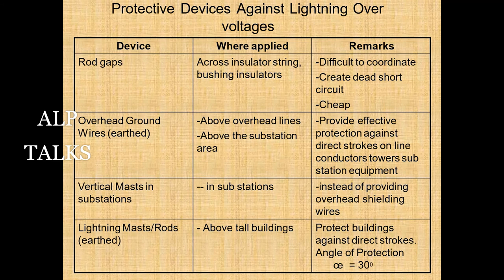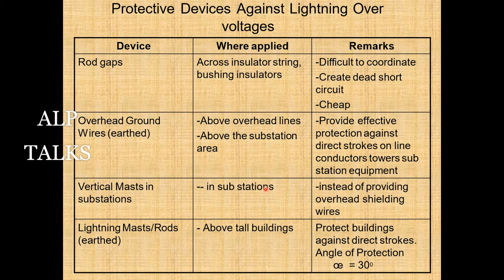Rod gaps are a device for protecting against lightning overvoltages across insulator strings and bushing insulators, though coordination is difficult as they create a dead short circuit. Overhead earth wires above the substation area provide effective protection against direct strokes on line conductors, substation equipment, and service buildings. Alternatively, vertical masts in substations can replace overhead shielding wires. Lightning masts or rods earthed above tall buildings protect against direct strokes, with an angle of protection generally 30 degrees.